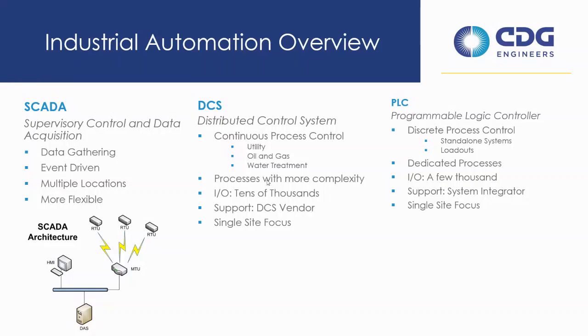Another difference between the two for SCADA and DCS and PLCs is single site focused versus remote locations, like I said. A DCS or a PLC system is really going to be at a central location. It might communicate some information back to another site via radio or cellular communication, but it's not going to control 400 different sites - it's really going to control one site, because it's too much I/O, too much traffic on that communication stream to take all that control process over a communication network.